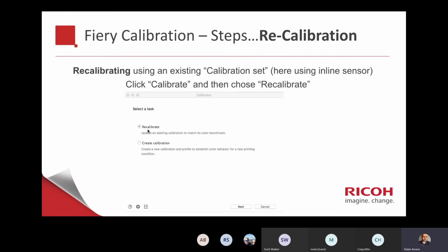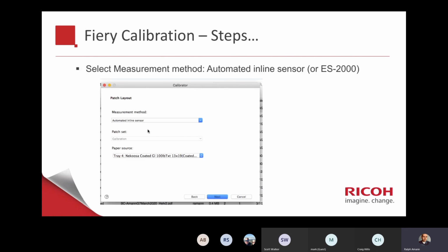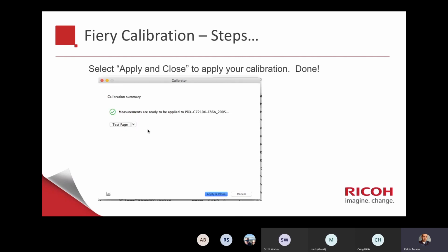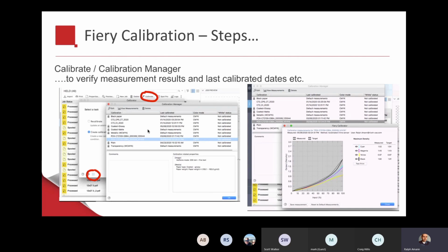Then, just 2 slides, really fast. If you choose to recalibrate, which is what you're probably going to do most of the time after finding out what we're using in our environment, you just hit recalibrate as an option. You select what device, and if you have an automated inline sensor on the C7200 or C9200, then you're basically done, because the machine does it for you and updates everything. If you select a device like the ES2000, then you still have to select the patches. So, calibration done with that.